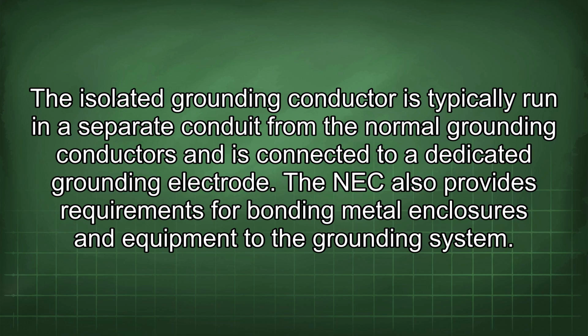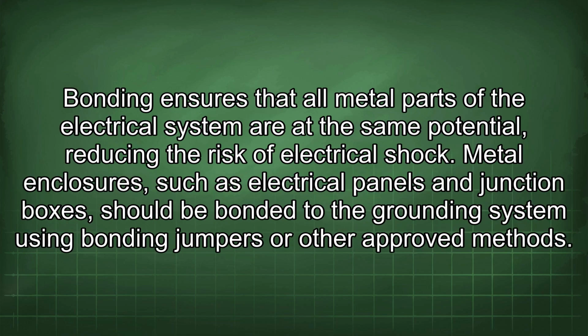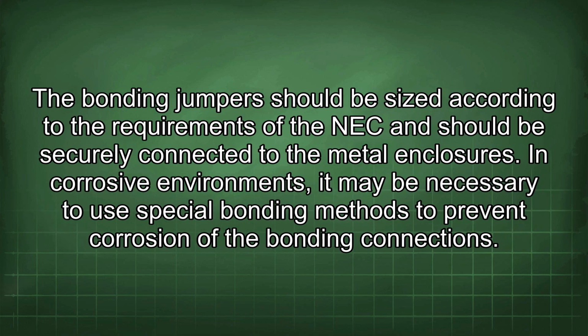The NEC also provides requirements for bonding metal enclosures and equipment to the grounding system. Bonding ensures that all metal parts of the electrical system are at the same potential, reducing the risk of electrical shock. Metal enclosures, such as electrical panels and junction boxes, should be bonded to the grounding system using bonding jumpers or other approved methods. The bonding jumpers should be sized according to the requirements of the NEC and should be securely connected to the metal enclosures. In corrosive environments, it may be necessary to use special bonding methods to prevent corrosion of the bonding connections.